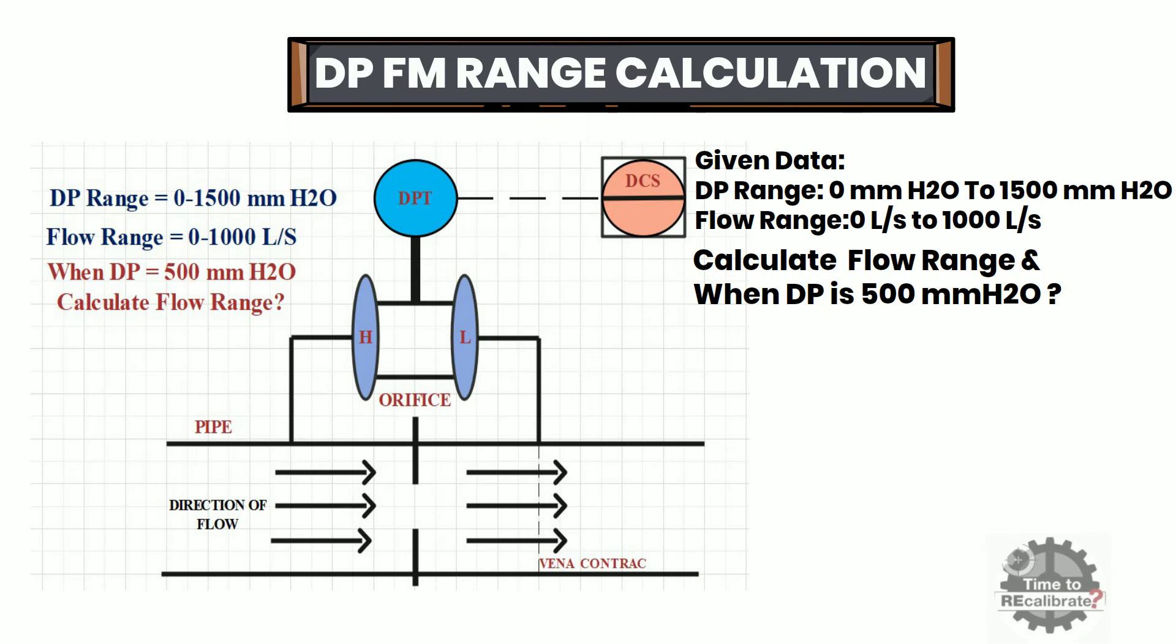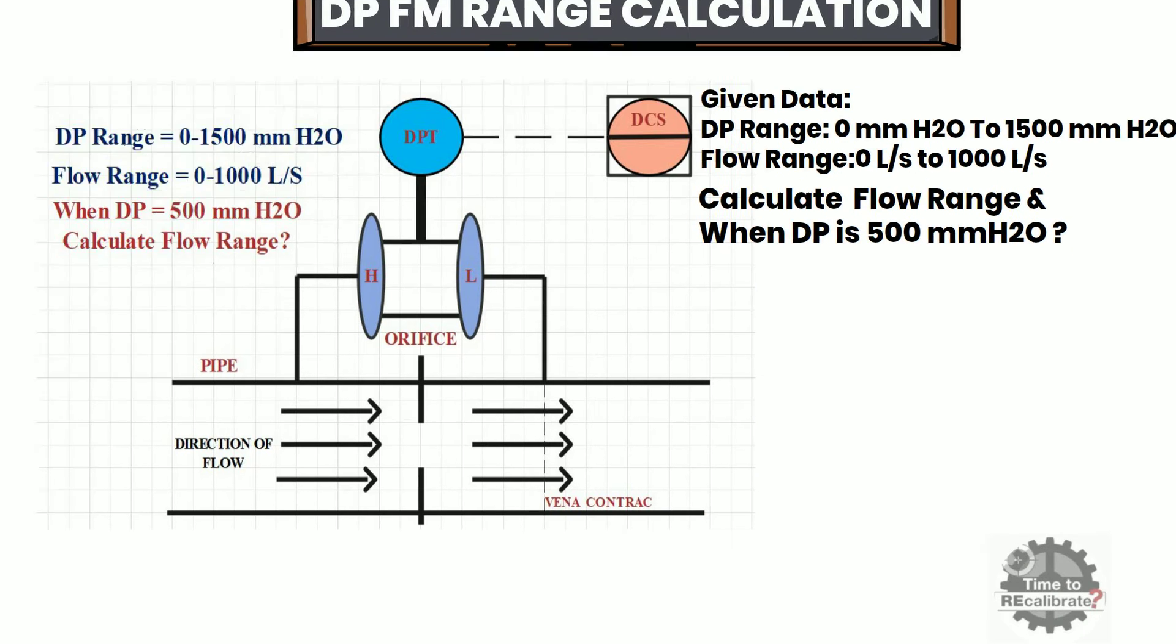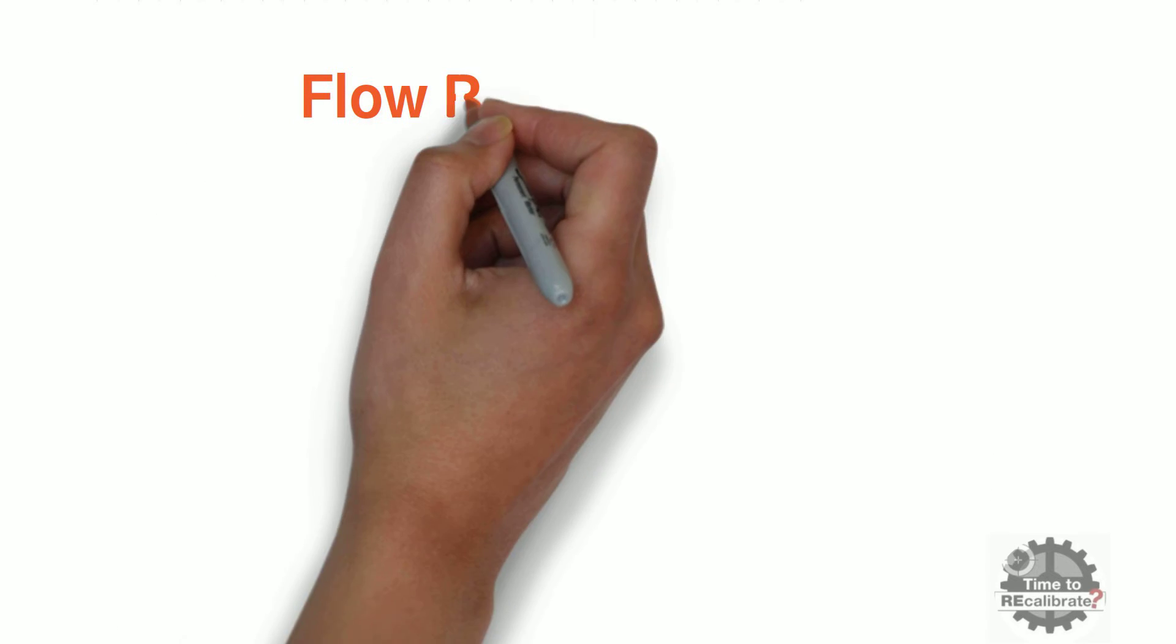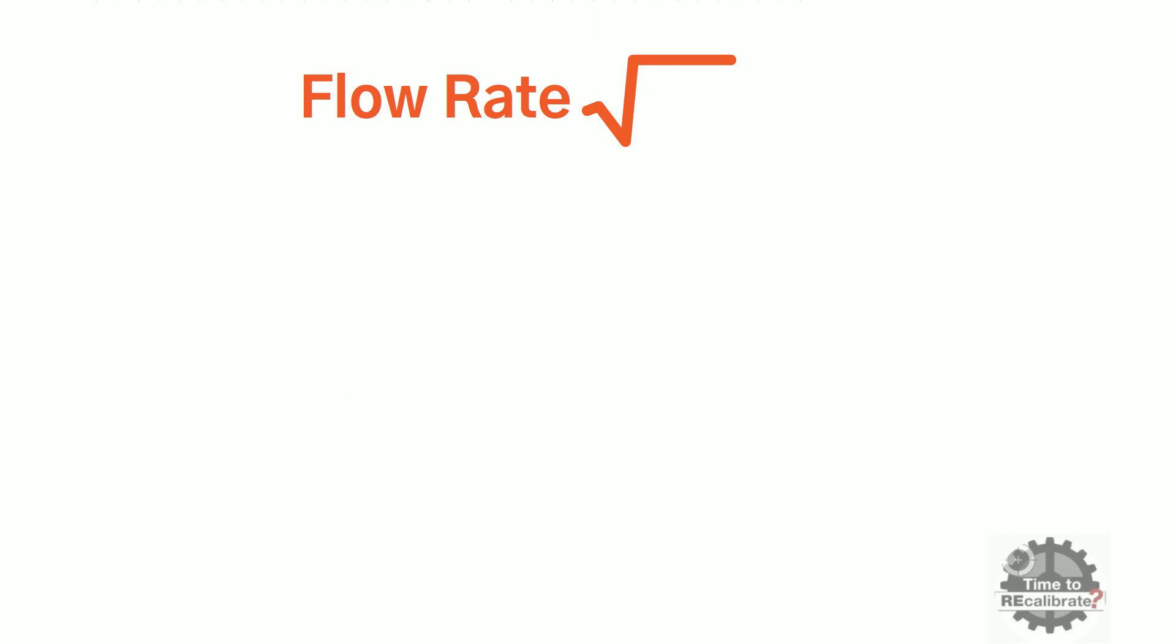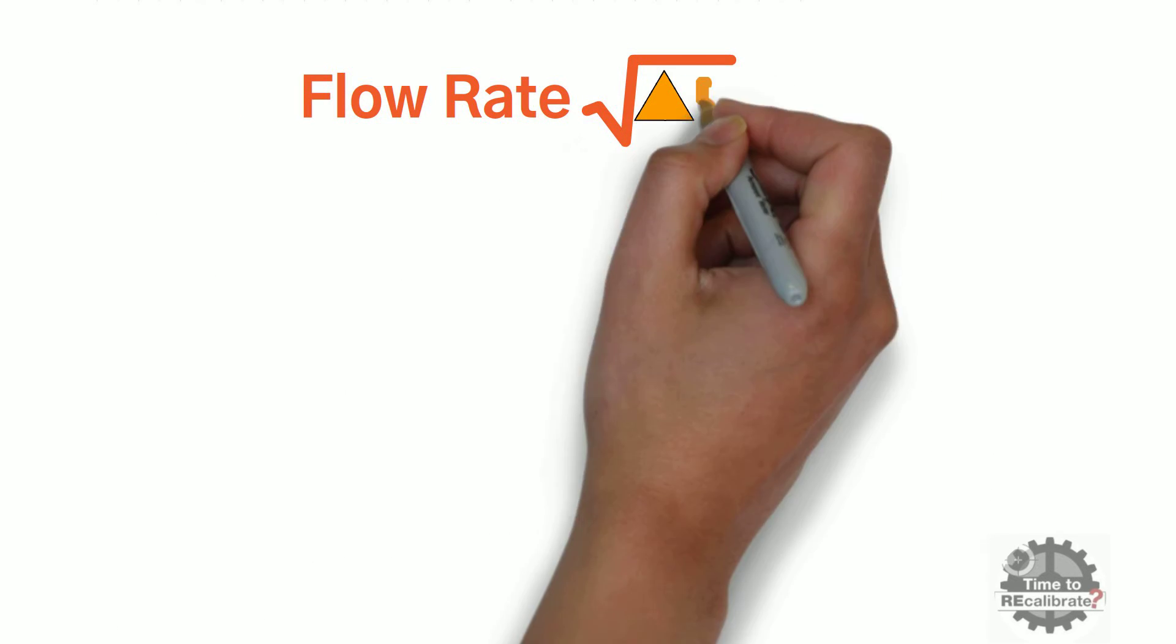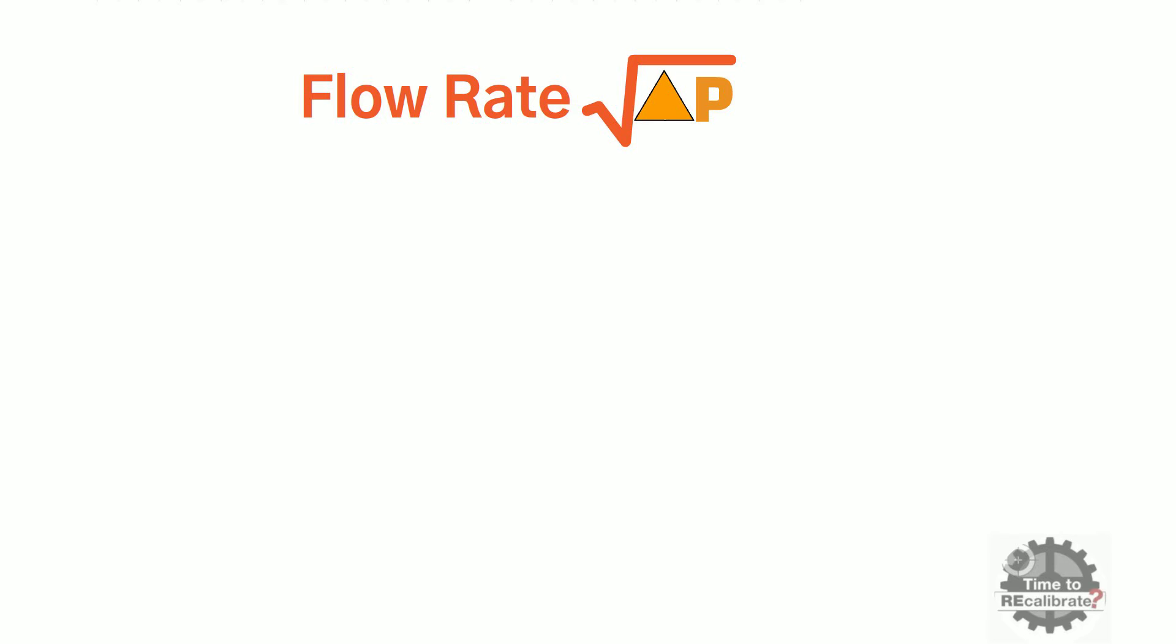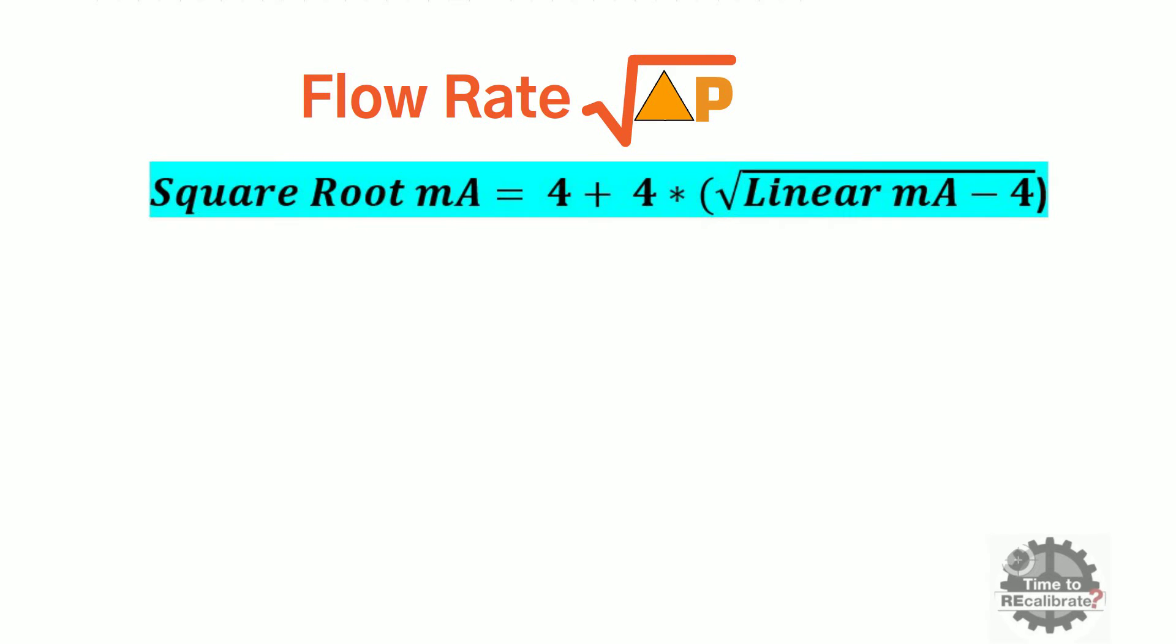Now let's go to the calculation. As we know, flow rate is directly proportional to the square root of differential pressure. So to calculate the flow range of a DP flow meter, we need to calculate square root milliampere first. This is the standard equation to calculate square root milliampere. As you can see from this equation, we need the linear milliampere value to find the square root milliampere.